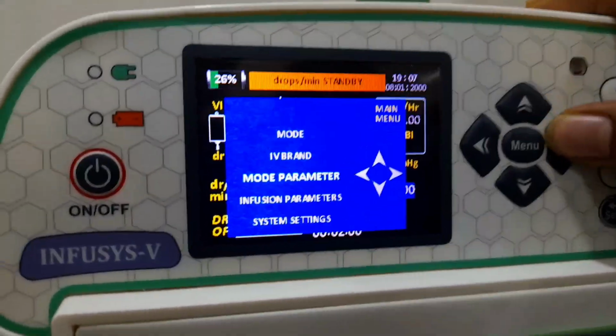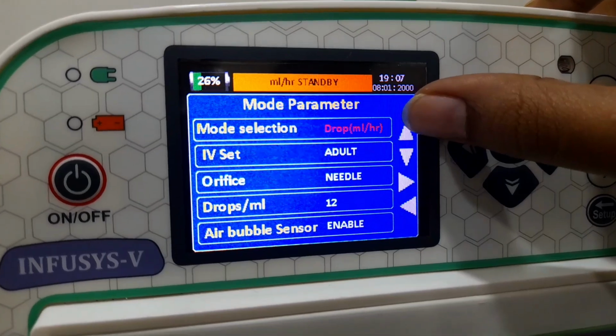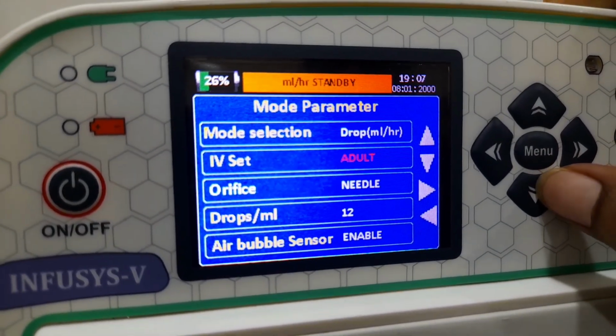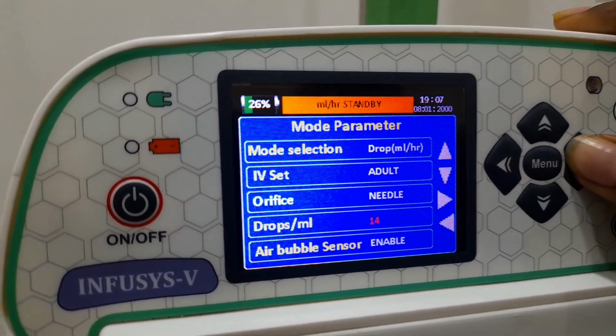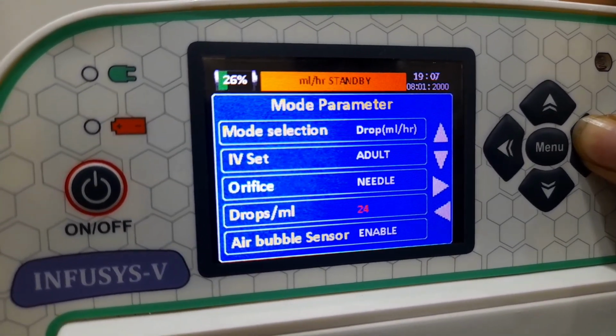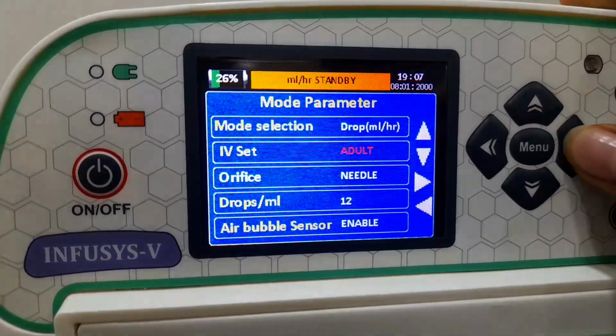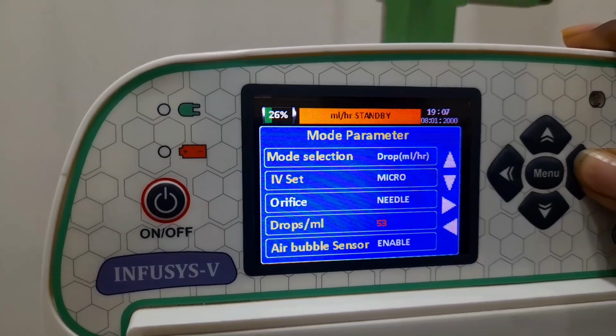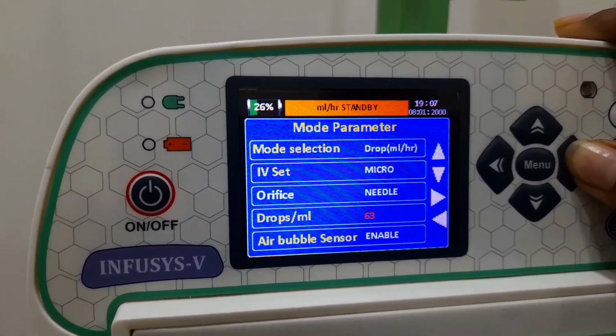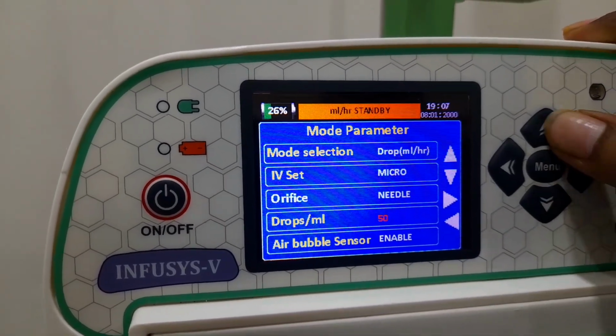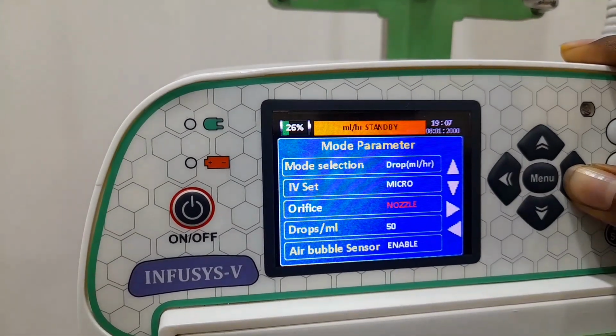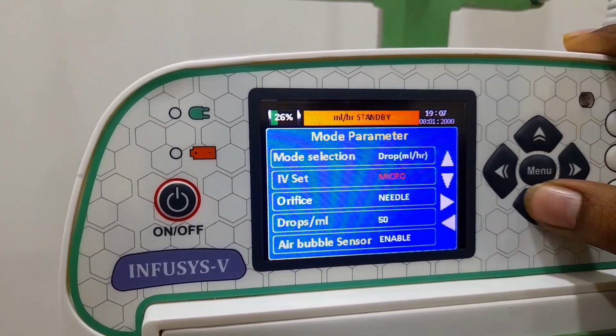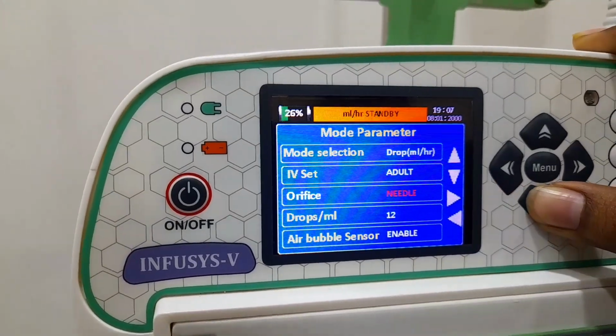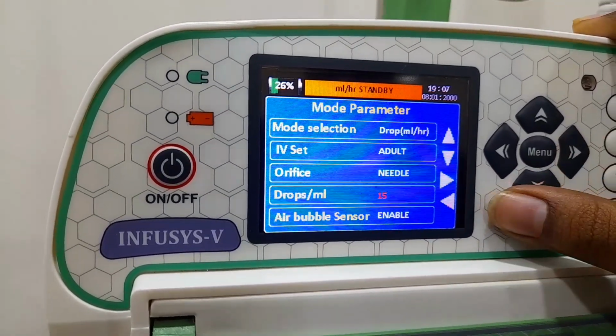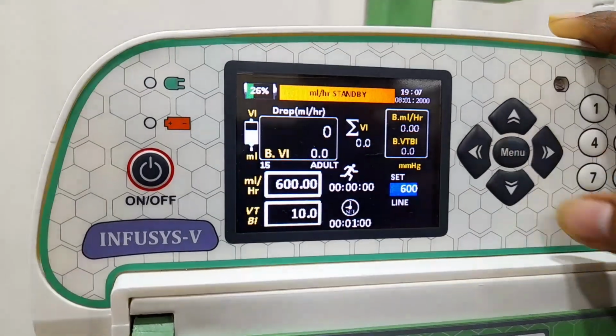Next, we move to the infusion parameter and change the mode selection to drops ml per hour. Here, based on the IV set, drops per ml will change. For adult, we can change the drops per ml from 12 to 26 drops per ml, and in micro, 50 to 66 drops per ml. So here again we are going to use the IV set as adult, and we set the drops per ml as 15 drops per ml. Now we can start the infusion.